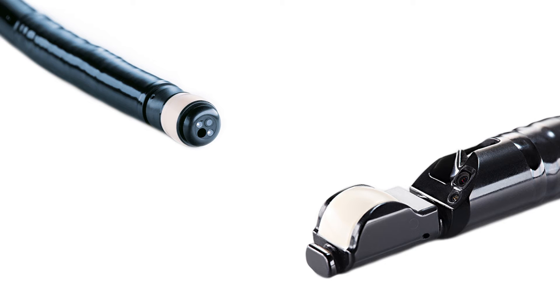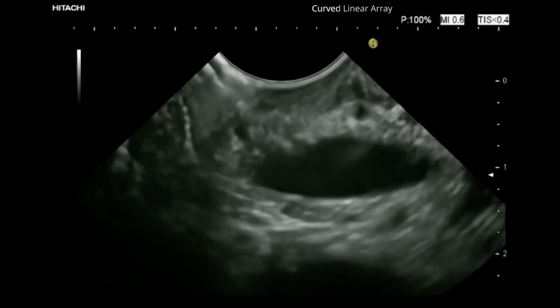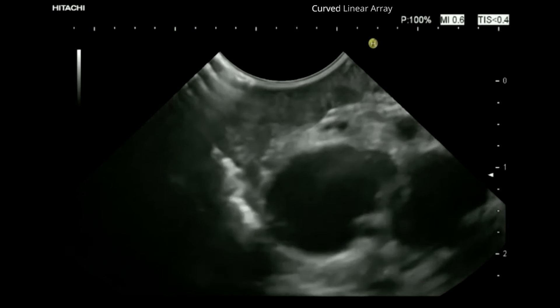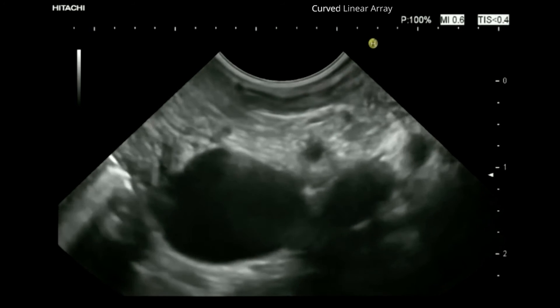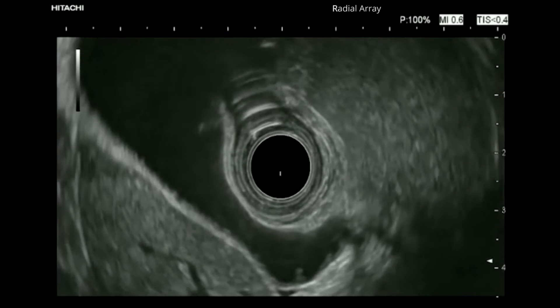Typical components at the distal end of ultrasound endoscopes include the ultrasound transducer, which transmits and receives ultrasound waves using the effect of piezoelectricity. Inside the transducer there are one or more piezoelectric crystals. When electrical pulses are applied, the crystals oscillate and produce ultrasound waves. When ultrasound waves are reflected back from tissue, the crystals oscillate and produce electrical pulses. A curved linear array transducer images in a plane parallel with the axis of the endoscope, while a radial array transducer images in a plane perpendicular to the axis.